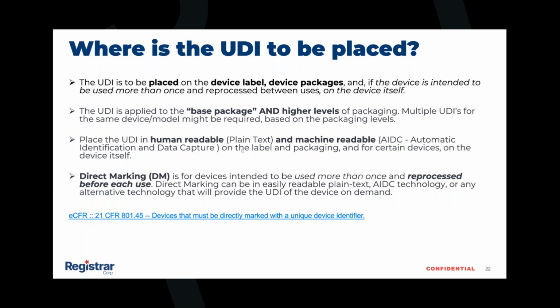So I just want to say that UDI is part of your barcode, but when you're in the issuing agencies, you'll see the word GTIN, which is your Global Trade Item Number. GTIN and your UDI are the same thing. It's just that in your issuing agency, GTIN is the word you'll be seeing. Okay, it's important to place the UDI in human readable plain text and machine readable AIDC, automatic identification and data capture, on the label and packaging for certain devices and the device itself.